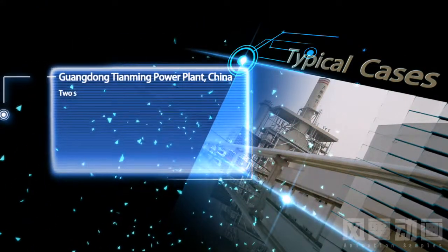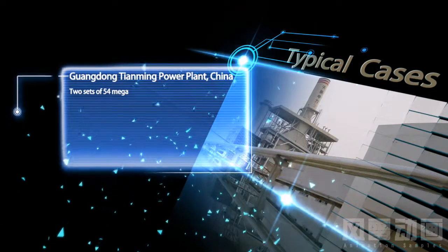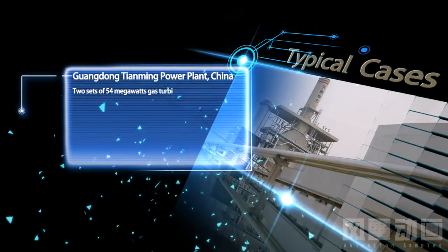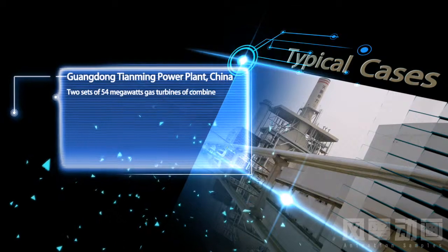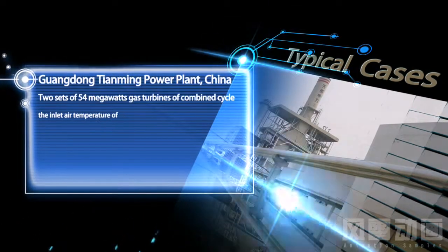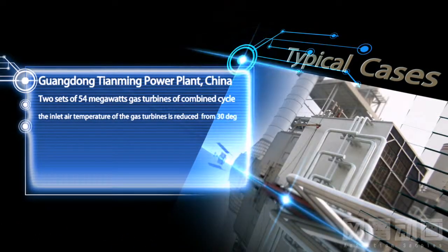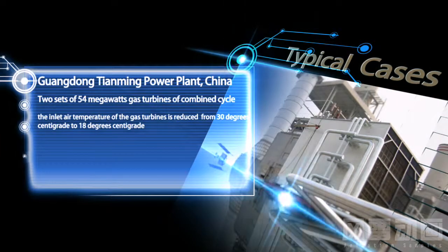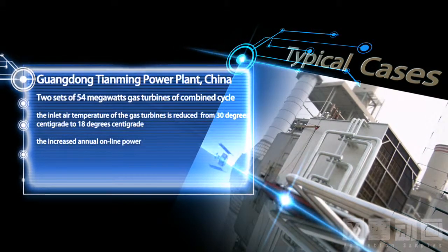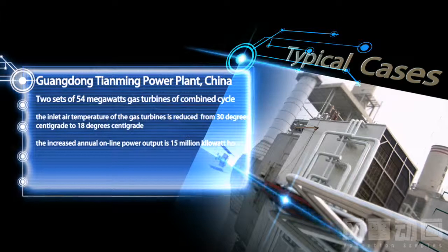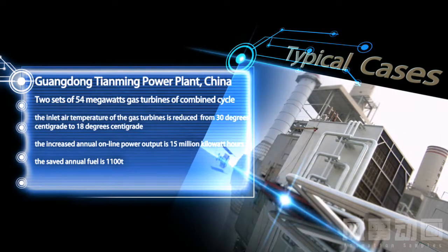2 sets of 54 megawatts gas turbines of combined cycle at Guangdong Tianming Power Plant, China. After adopting the air inlet cooling system, the inlet air temperature of the gas turbines is reduced from 30 degrees centigrade to 18 degrees centigrade. The increased annual online power output is 15 million kilowatt hours. The saved annual fuel is 1,100 tons.